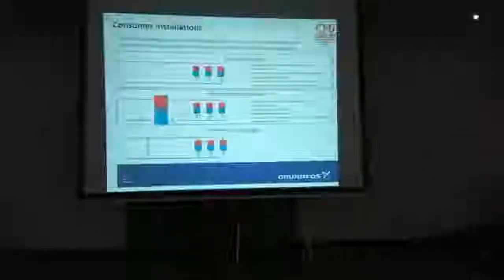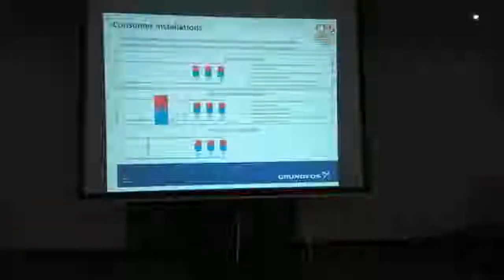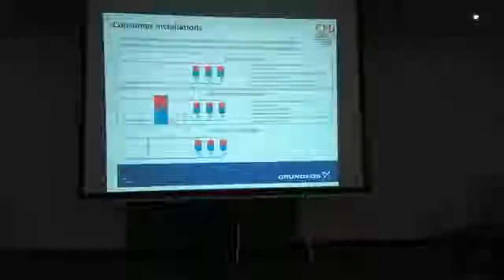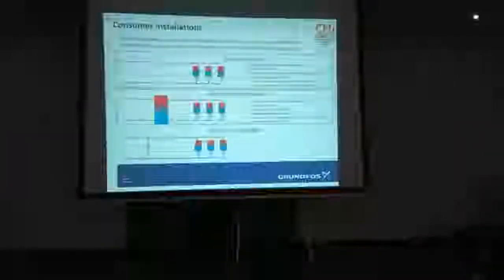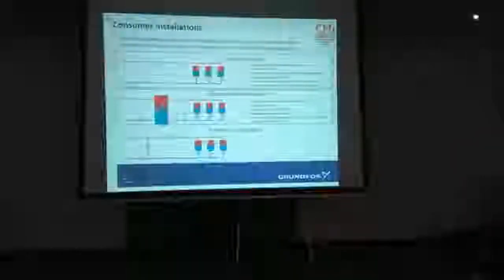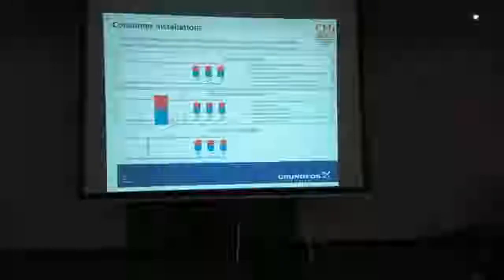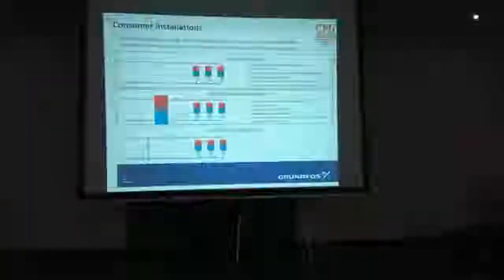In other words, block of flats, or 2 or 3 blocks of flats, and there's 3 people moved in. For the first 6 months, that's going to be an absolute nightmare to control. If you've got some sort of thermal store in that area there, it's okay. It doesn't matter coming back to the thermal store at high temperature or low differential. These are just tips, but you've got to have a big area for the thermal store. And how big you need.